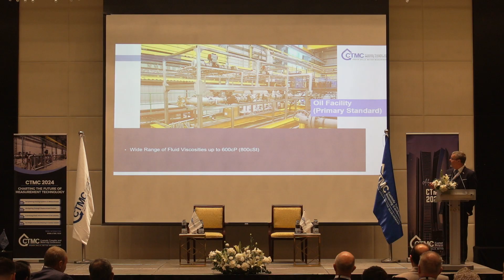We have a Coriolis meter, and we've calibrated it in kerosene at 2 centistoke. Yep, everything's fine. It's within the industry expectations, and it's within the manufacturer's specification. What happens if I increase the viscosity? So everything's fine for a low viscosity calibration. What if I send that to one of the high viscosity fields that we have in this world, or Venezuela, or Canada? A dramatic shift in performance. Absolutely huge shift in performance. As much as 1.5% in the worst case scenario.